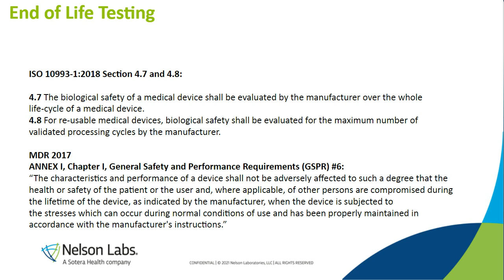Now, ISO 10993, this slide right on the top, section 4.8, specifies that for reusable medical devices, biological safety shall, as you all know, be evaluated for the maximum number of validated processing cycles by the manufacturer. Because there's a shall there, that mandates that you should have that information. But if you look at the MDR, it says that if the device is reusable, information on the appropriate process for allowing reuse, including cleaning and disinfection, shall be provided, to identify when the device should no longer be reused, such as signs of material degradation or the maximum number of allowable uses.